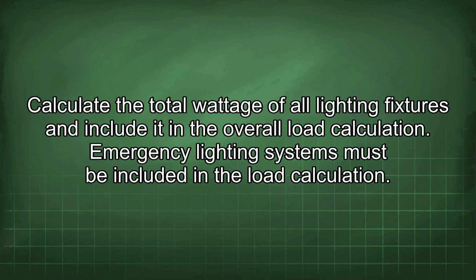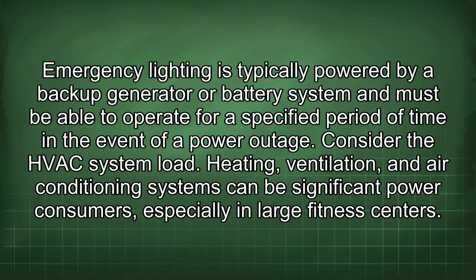Calculate the total wattage of all lighting fixtures and include it in the overall load calculation. Emergency lighting systems must be included in the load calculation. Emergency lighting is typically powered by a backup generator or battery system and must be able to operate for a specified period of time in the event of a power outage.